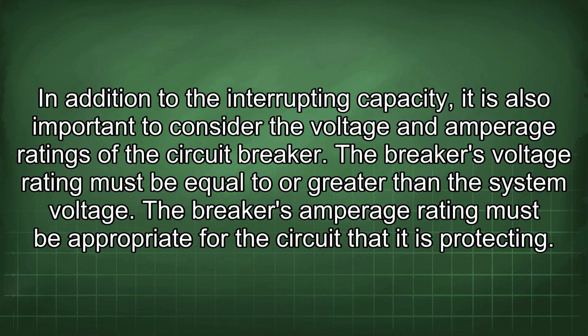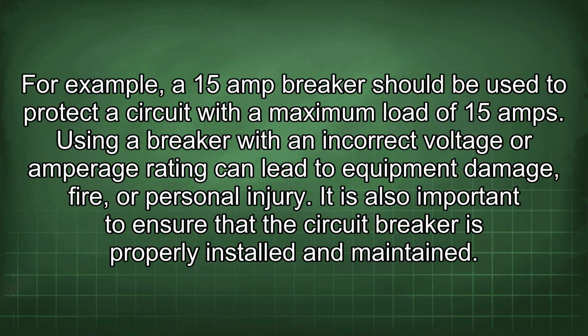In addition to the interrupting capacity, it is also important to consider the voltage and amperage ratings of the circuit breaker. The breaker's voltage rating must be equal to or greater than the system voltage. The breaker's amperage rating must be appropriate for the circuit that it is protecting. For example, a 15 amp breaker should be used to protect a circuit with a maximum load of 15 amps. Using a breaker with an incorrect voltage or amperage rating can lead to equipment damage, fire, or personal injury.